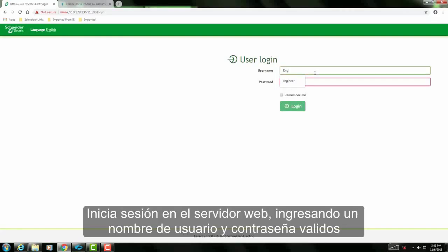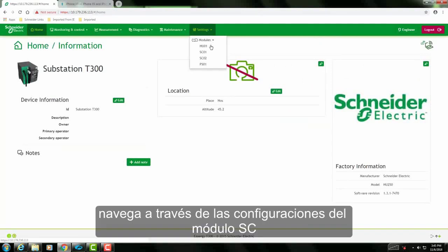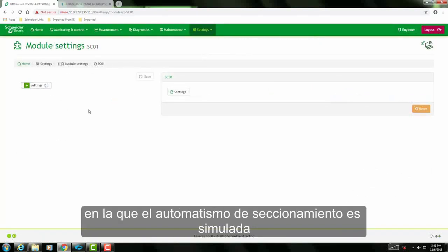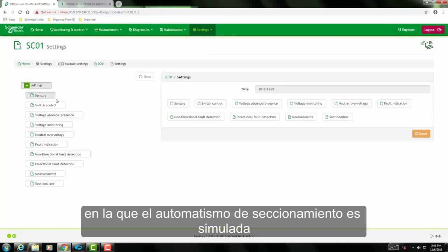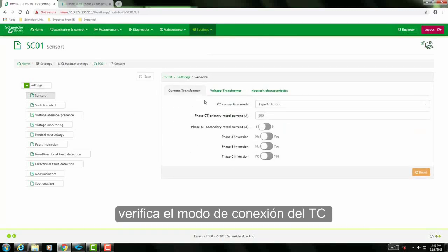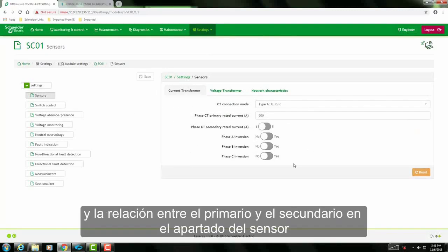Settings: log on to the web server by typing in the right username and password. Navigate to the settings of the SC module on which the sectionalizer automation is being simulated. Ensure the right CT connection mode and the primary-secondary ratios in the sensor section.